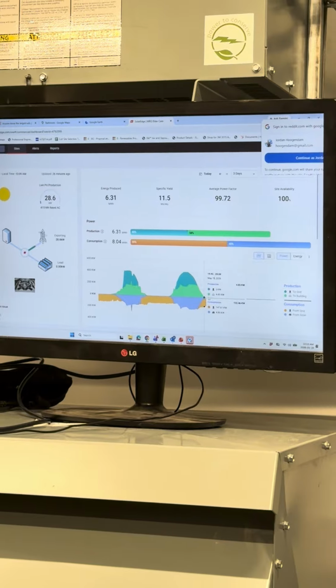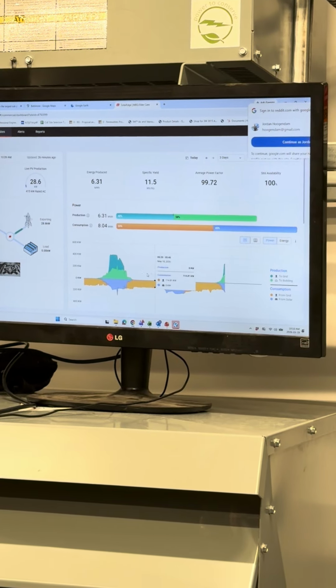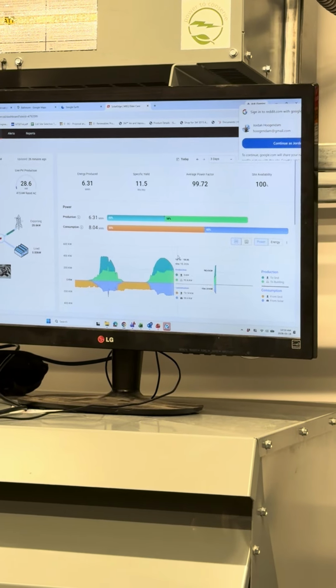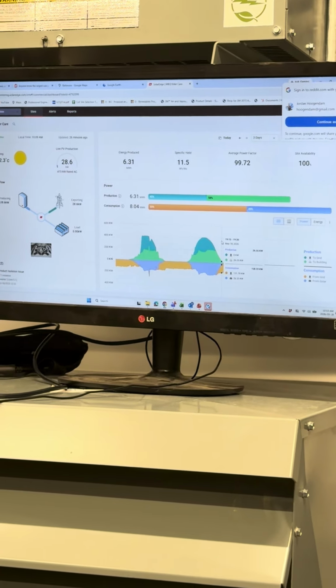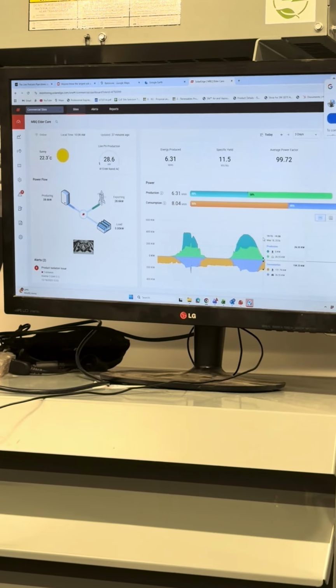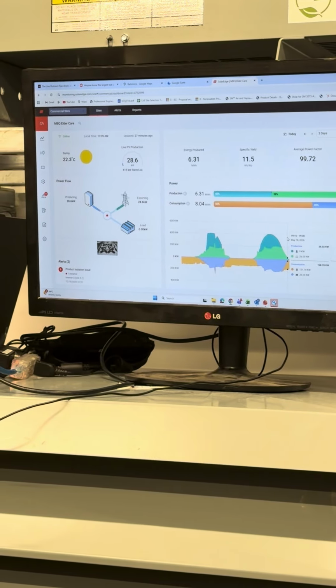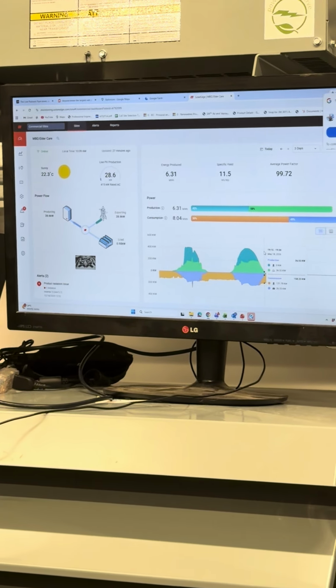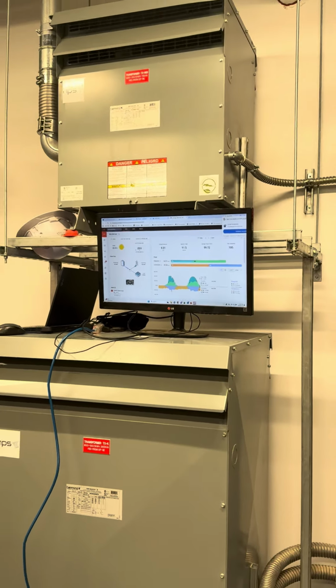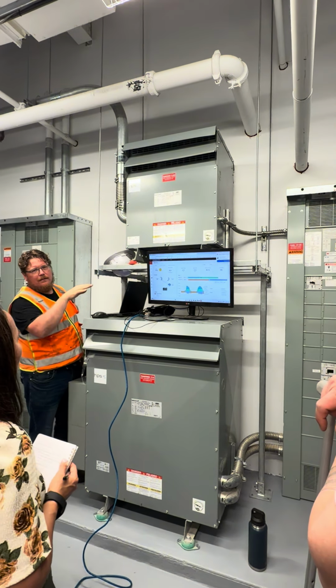The other thing to keep in mind when you're looking at the monitoring is this 400 kilowatts is our peak output. So if you saw that curve peaking out below 400, say at 350 or 300, that's a pretty good indication, if it's a sunny day, that there's an inverter offline. So that's a chance to go look at the faults.